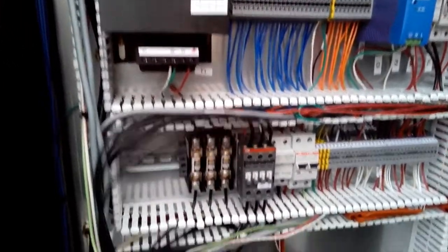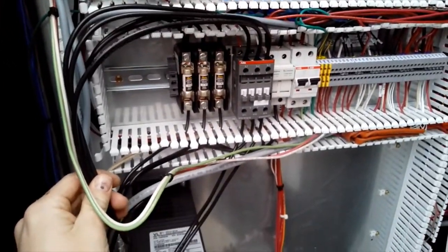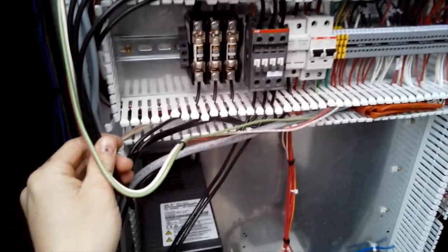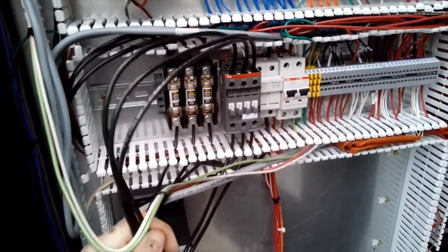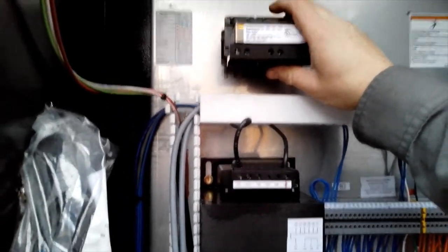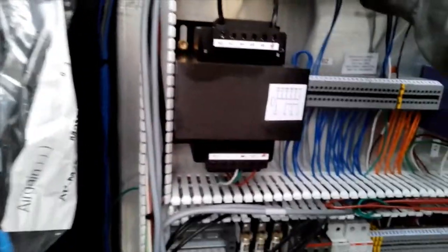So essentially, we want to put this line reactor in between the fuses and the VFD. I'm going to take the wire from the bottom of these fuses, take this out, and we'll mount the line reactor right up here, and then we will go back to the top of that contactor.